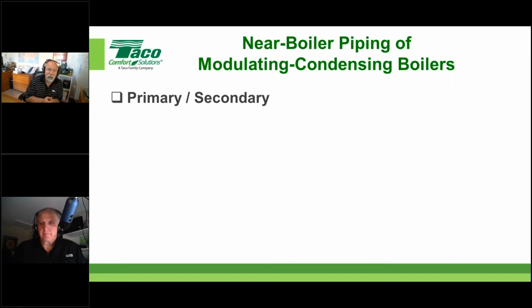You don't always have to pipe primary secondary with a condensing piece of equipment. And you go, what? No, always refer to what the manufacturer shows you in their book. Plenty of these manufacturers show you both. They show it piped in series, which means not primary secondary, or they show it primary secondary, and they'll give you plenty of information to tell you why they're doing what they're doing, and they'll give you the appropriate sizing information, which we're going to review today as well.